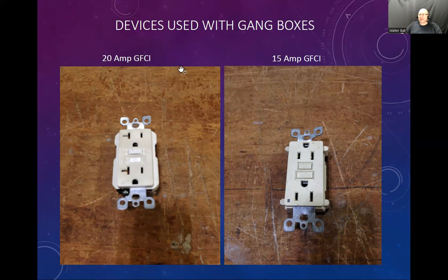It has to have the ampacity of 20 amps. Otherwise, if you have the circuit breaker rated for 20 amps and this receptacle rated for 20 amps, but you have thinner wire than you should have, you could find yourself in trouble. Basically, you can heat up those wires to the point that you can actually start a fire.